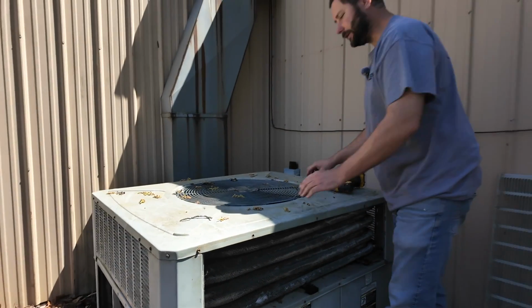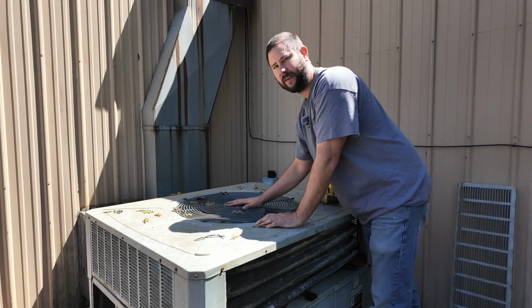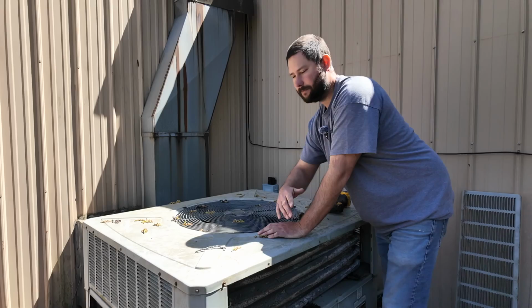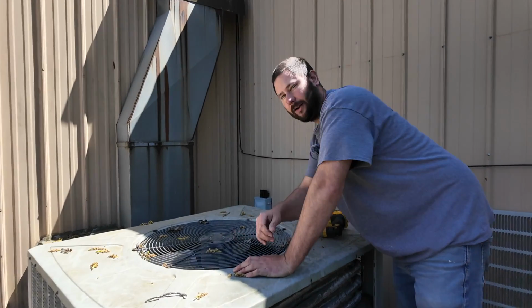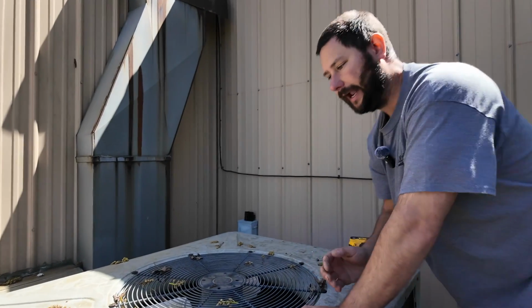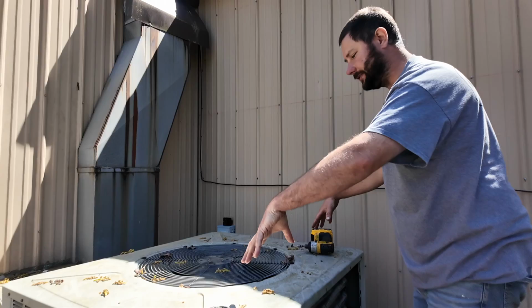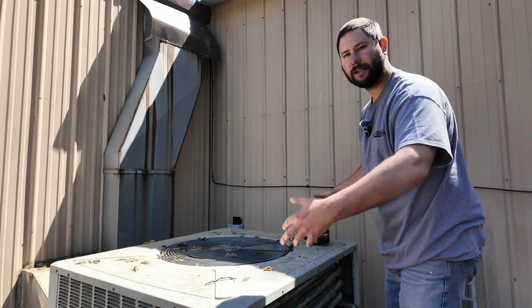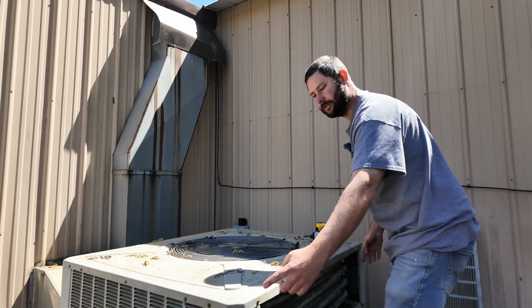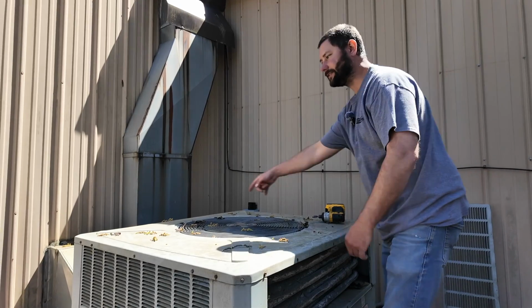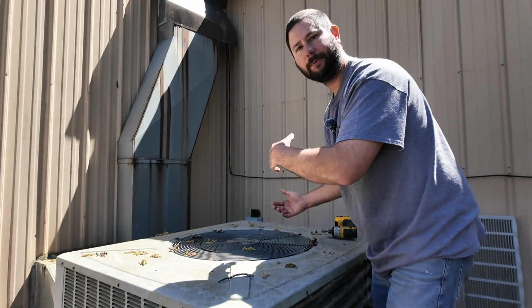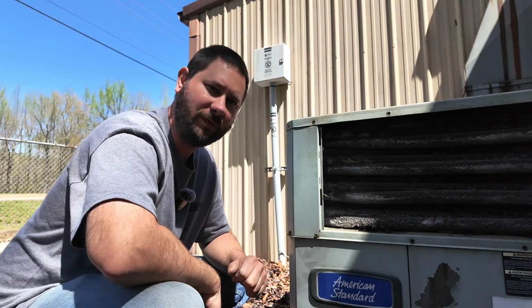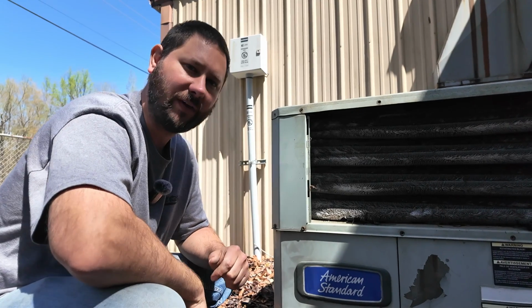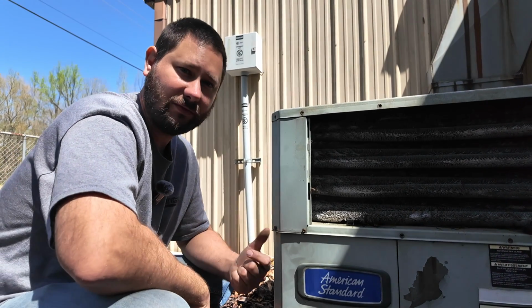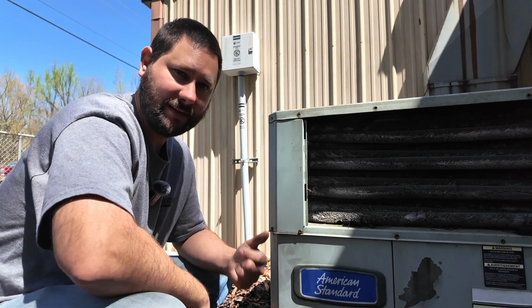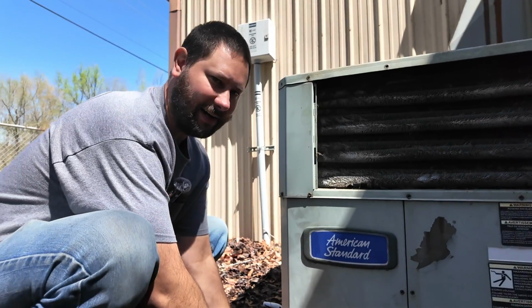One is we could just remove the screws from this fan mount and then just fold the fan back and then spray from the inside out. But I don't like to do that. I like to actually be able to get my hands in there and make sure I clean every crevice. So I'm just going to take the screws out of the top and then remove the whole top. We cannot remove the top unless we disconnect the fan wiring, because if the fan wires are connected and we try to take the top off, it's just not going to work.